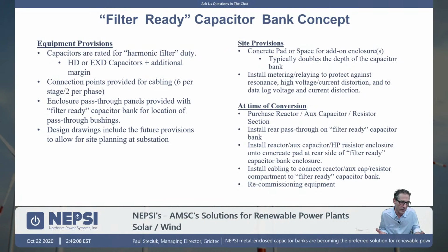which means you have to buy more kVAR up front, but the cost per kVAR, when you're just talking about kVAR, is very inexpensive. So it's pennies on a dollar at this point to install that higher rated capacitor that you would need if it were to get converted to a harmonic filter. Provide the provisions for that, and this is whether it's open air or metal enclosed, you should be thinking about filter ready all the time.